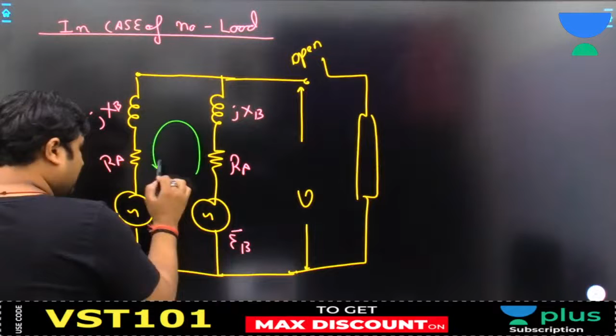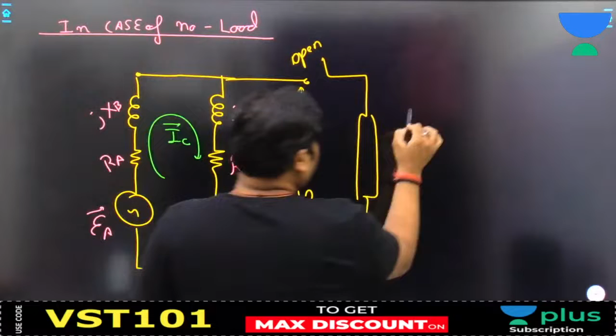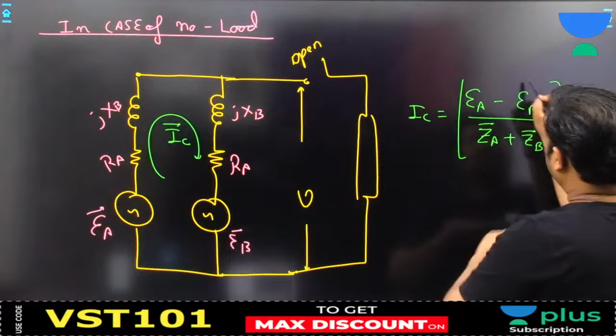We have assumed that EA is greater than EB, so a current will start flowing from one transformer to another transformer. This current is called circulating current, and the magnitude of circulating current is EA minus EB, higher potential minus lower potential, upon ZA plus ZB. Always remember that they may differ in magnitude, but they are always in the same phase. So EA and EB may differ in magnitude, but EA and EB are always in the same phase. Keep that in mind.